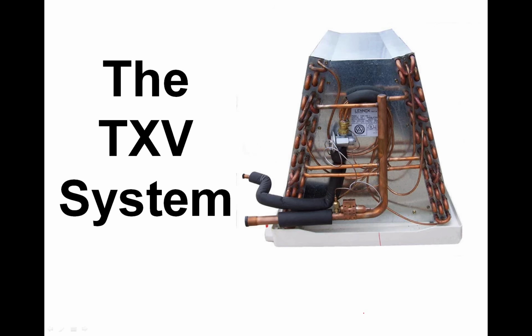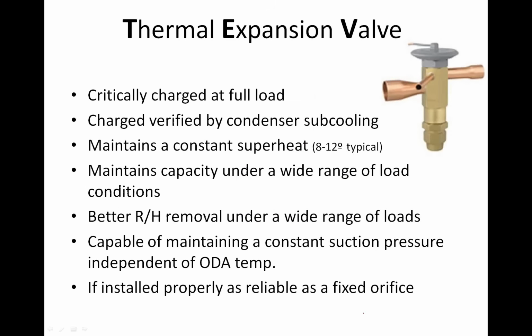All right. So TXV systems are critically charged at full load, and the charge is verified by condenser subcooling, and it maintains a constant superheat.